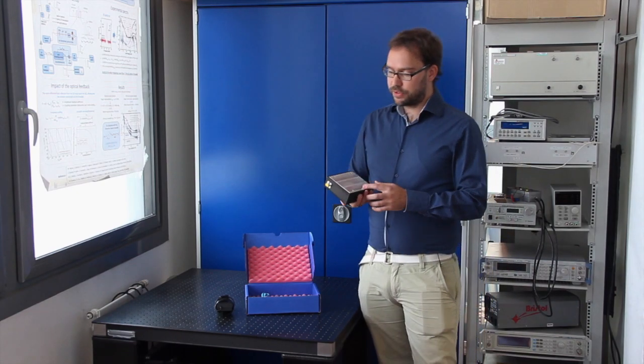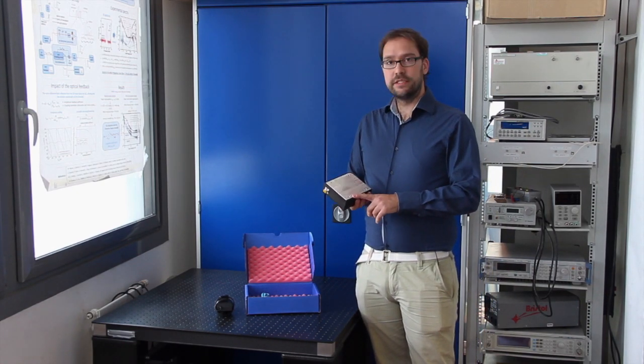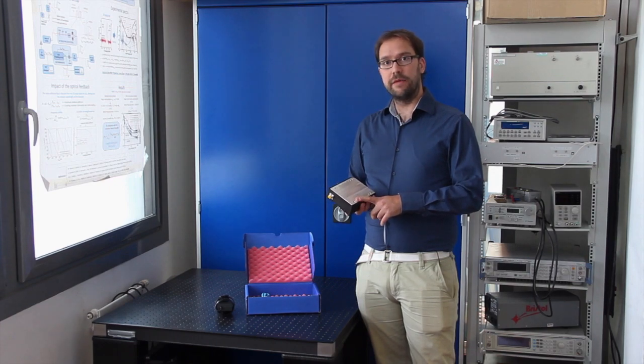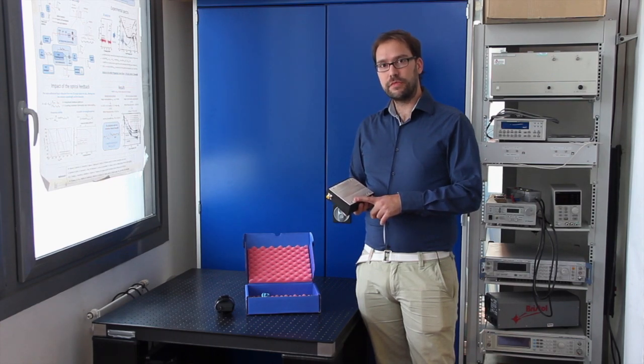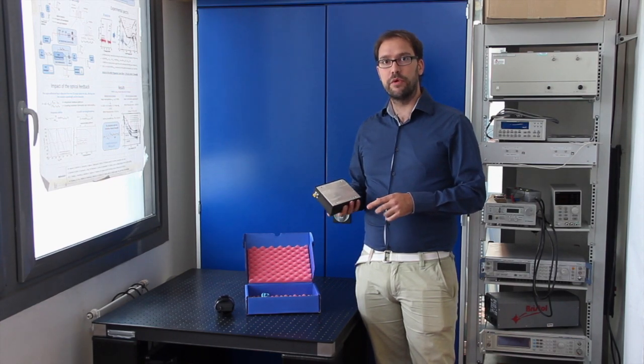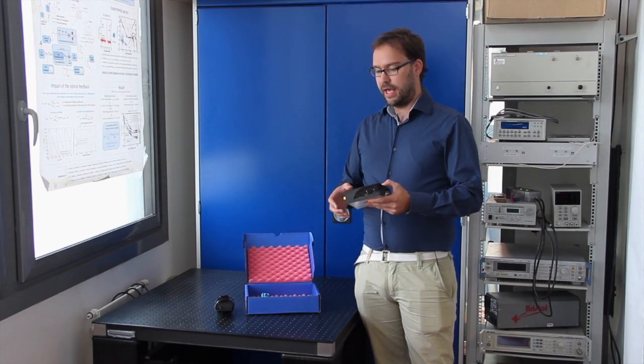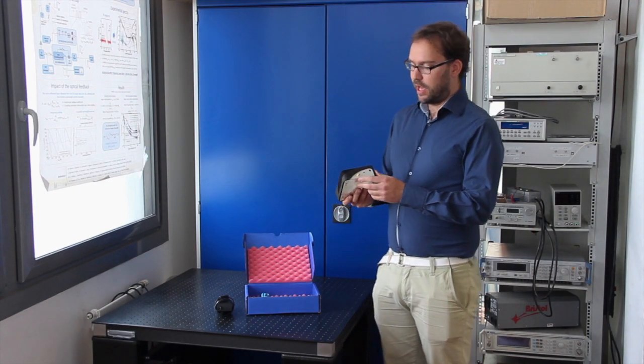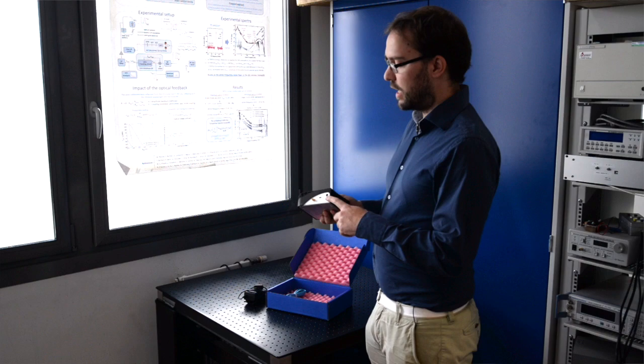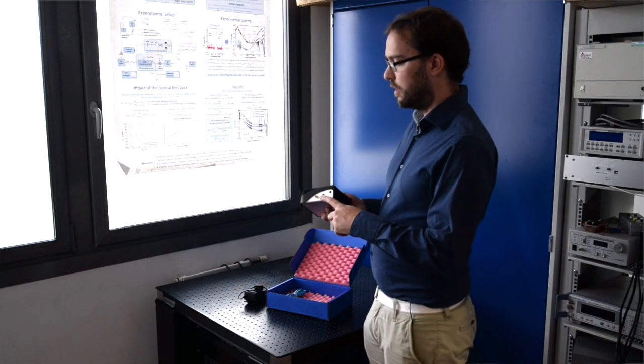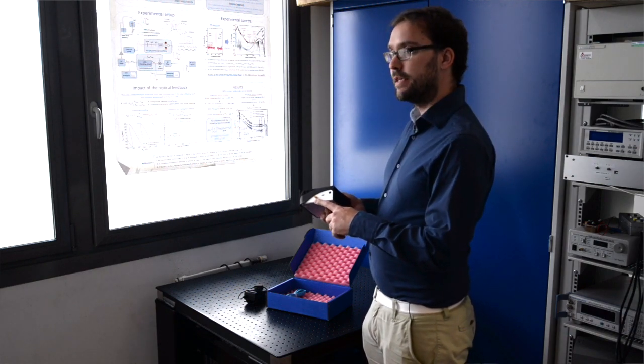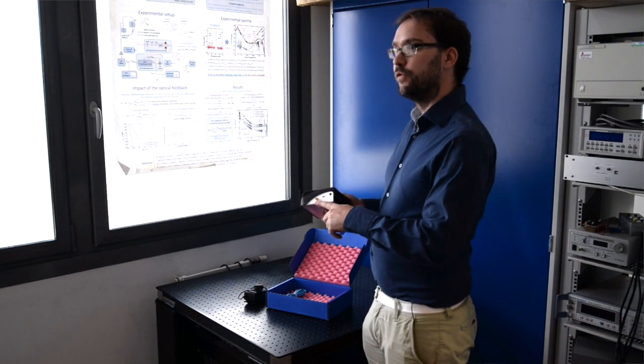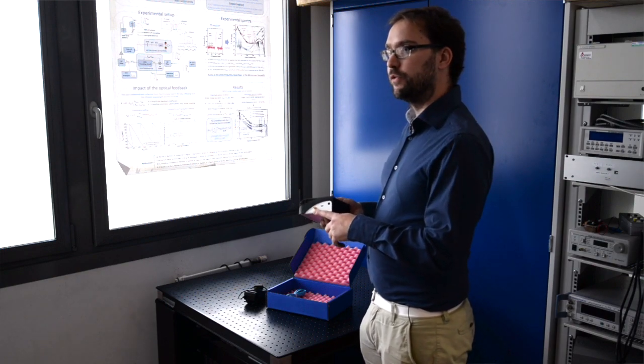At the back of the source we have eight threaded holes, four M6 and four M4 to mount the source on the setup or on the optical table. At the back we have the plug for the DC power supply, the micro USB cable, and this SMA connector is used for an external trigger of the source.